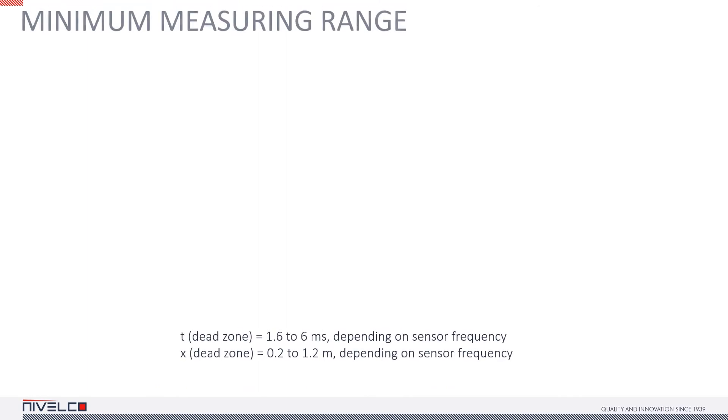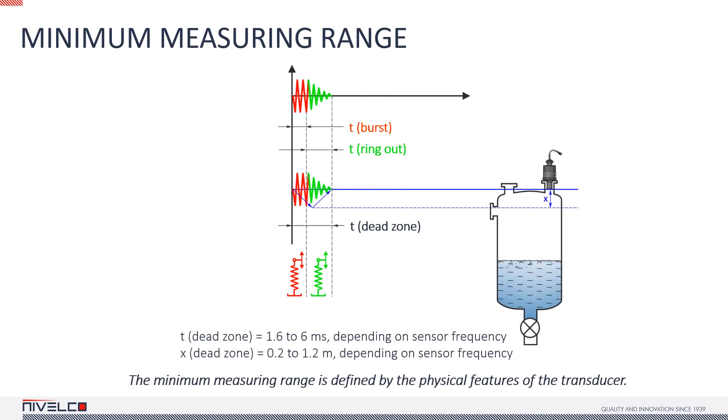We have discussed the maximum measuring range, but there is a minimum measuring range as well. The dead zone, within which measuring is not possible, is the distance covered by the sound waves during the time of the ultrasound burst, indicated as T-burst, and the ring-out time during which the burst fades out.